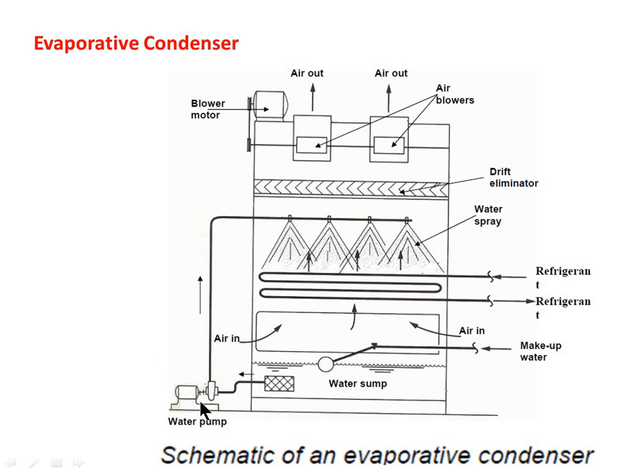A water pump provides water for the spray. Water is pumped from the sump to the spray header and sprayed through nozzles over the condenser coil, through which hot vapor refrigerant from the compressor passes. Heat transfers from the refrigerant through the condensing tube coils into the water wetting the outside surface of the tubes. A fan draws air from the bottom and discharges it at the top, causing water on the coil surface to evaporate and absorb the latent heat of evaporation.